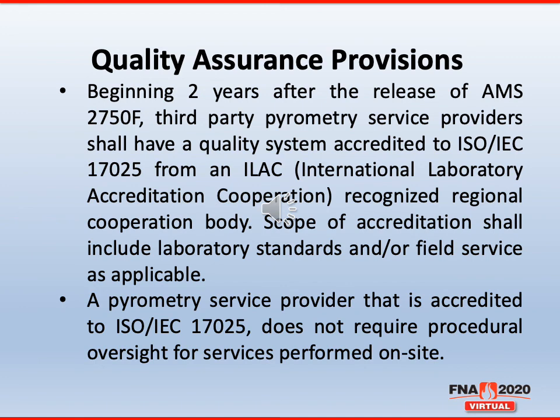Lastly, when it comes to the quality assurance provisions, beginning 2 years after the release of AMS 2750F, any third-party pyrometry service providers shall have a quality system accredited to ISO/IEC 17025 from ILAC, International Laboratory Accreditation Cooperation, recognized by regional cooperation bodies. Their scope of accreditation shall include laboratory standards and/or field service as applicable. A pyrometry service provider that is accredited to ISO/IEC 17025 does not require procedural oversight for services performed on site. So 2 years after the release, if you're having third-party calibrations done at your facilities, they will be required to be 17025 accredited for the field that they're doing calibrations or testing for you.